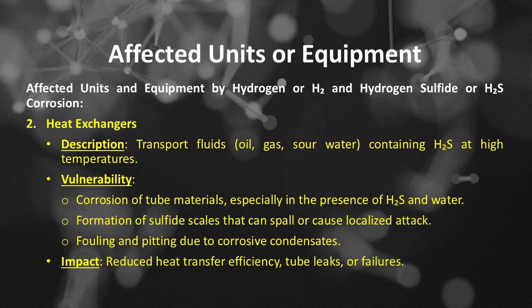The number 2 of the commonly affected units and equipment by high-temperature hydrogen or H2 and hydrogen sulfide or H2S corrosion is heat exchangers. It transport fluids, oil, gas, sour water, containing H2S at high temperatures. The vulnerability of high-temperature hydrogen or H2 and hydrogen sulfide or H2S corrosion to the heat exchangers, includes, corrosion of tube materials, especially in the presence of H2S and water, formation of sulfide scales that can spall or cause localized attack, fouling and pitting due to corrosive condensates. The impact of high-temperature hydrogen or H2 and hydrogen sulfide or H2S corrosion to the heat exchangers. It reduced heat transfer efficiency, tube leaks, or failures.